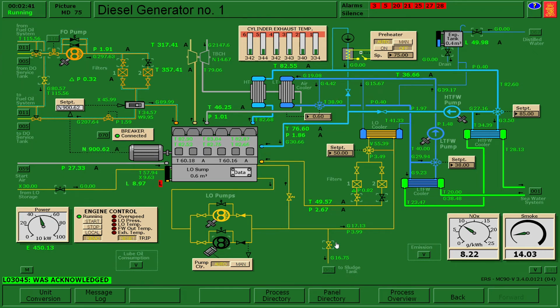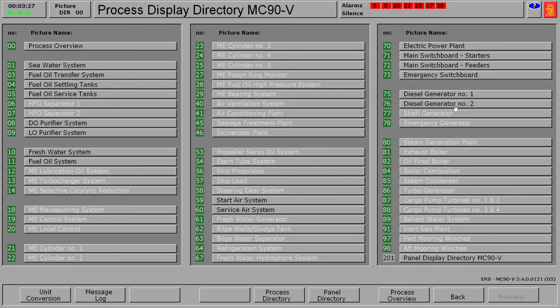And then we're just gonna go ahead and close our discharge valve, and then we're gonna open our makeup valve. And again, wait for this to set to 45 liters at least. We're just gonna wait for that. Okay, so that's already in 45 liters. Now let's proceed and go to DG2. We're gonna just monitor and check the parameters.